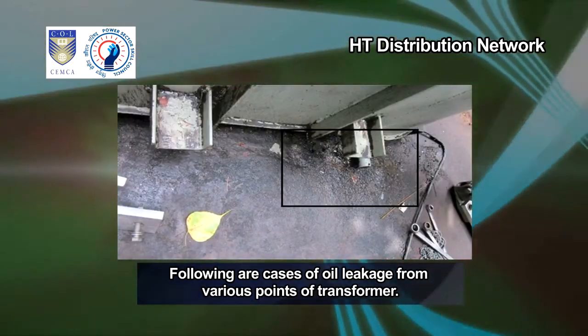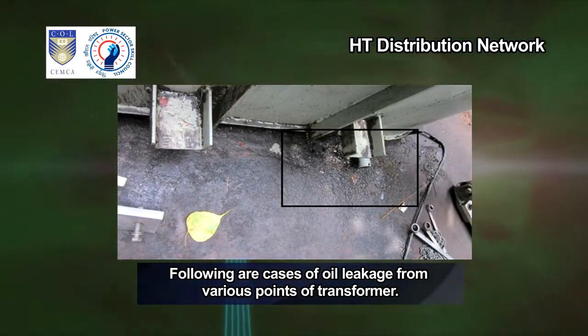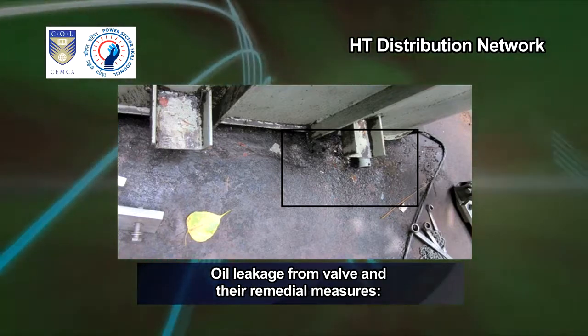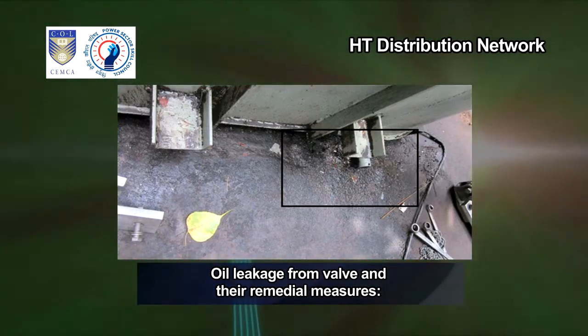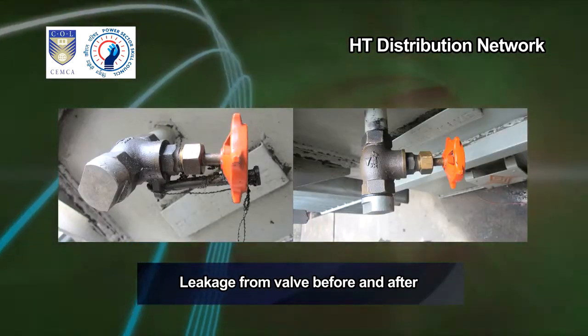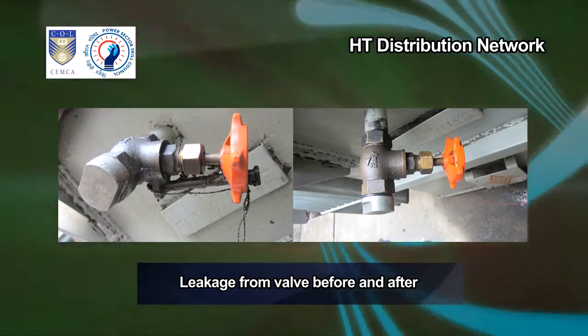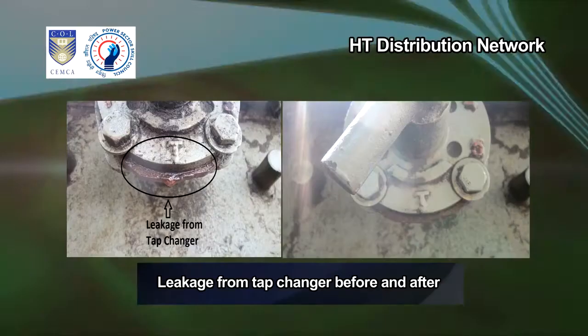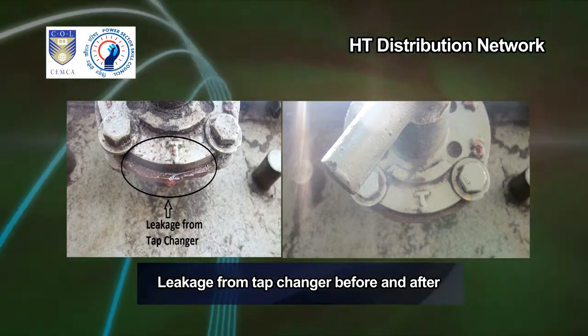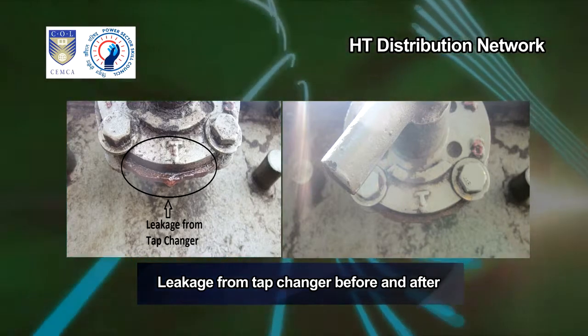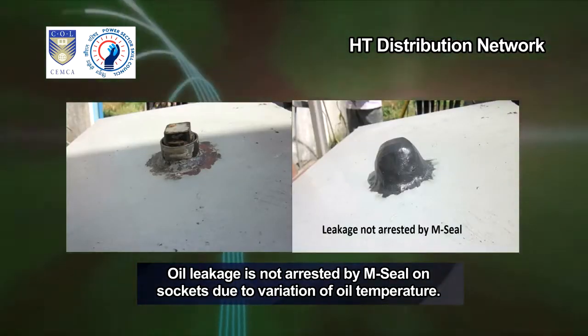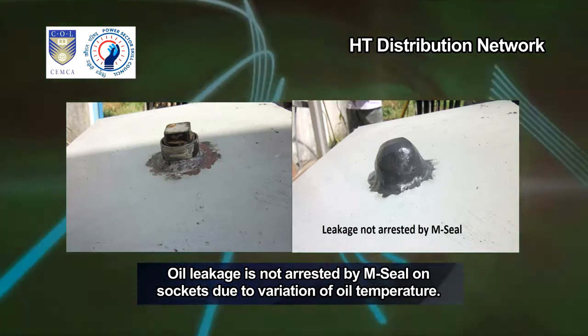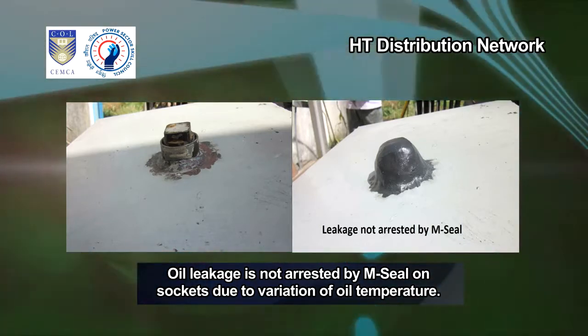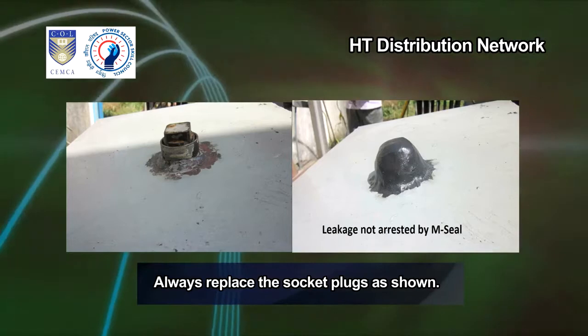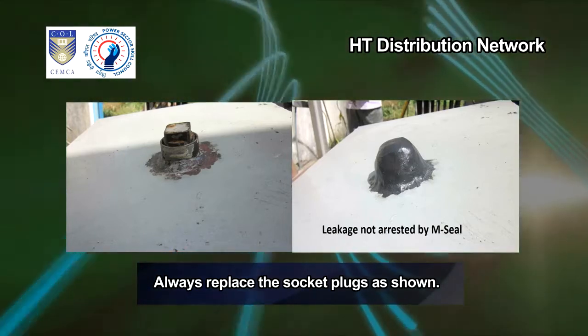Following are the cases of oil leakage from various points of transformer, oil leakage from valve and their remedial measures, leakage from valve before and after, leakage from tap changer before and after. Oil leakage is not arrested by M-seal on sockets due to variation of oil temperature. Always replace the socket plugs as shown.